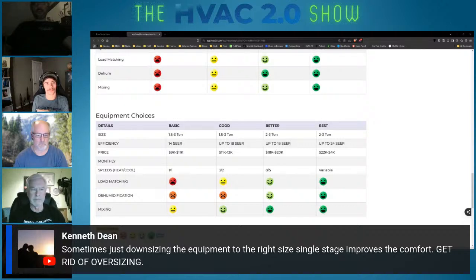All this equipment is getting installed with some kind of average static pressure of between 7 and 9, with a rated 0.5. One of the things we're finding is usually the ductwork, 95% of the time, is sufficient for the load of the house. So that leads me to believe if the ductwork is sufficient for the load of the house, but the measured static pressure on the equipment isn't appropriate to the ductwork, then the equipment is oversized.